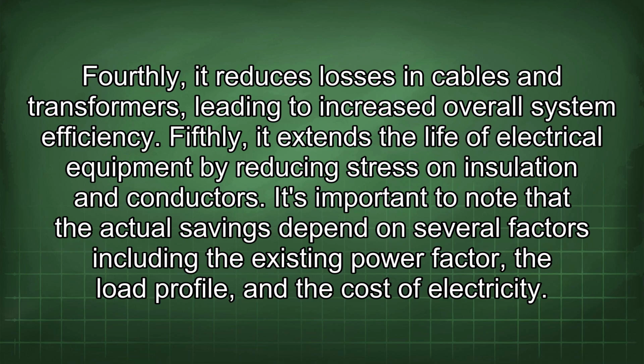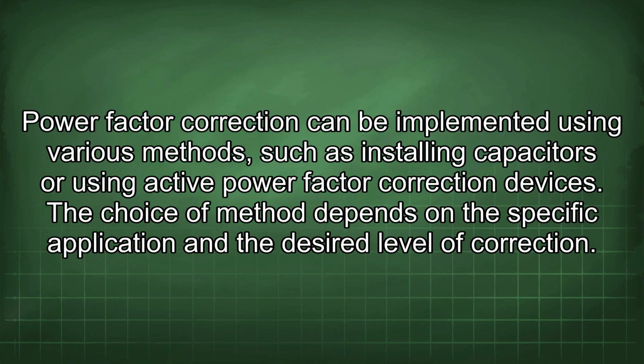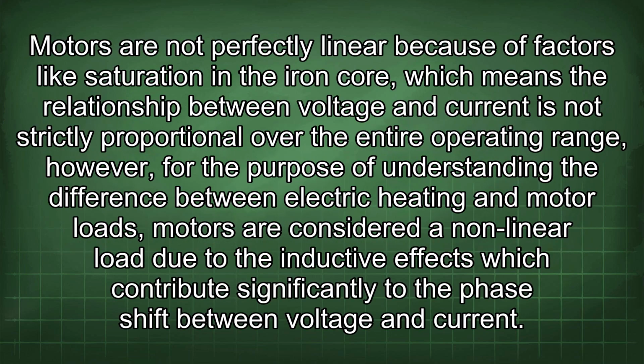It's important to note that the actual savings depend on several factors, including the existing power factor, the load profile, and the cost of electricity. Power factor correction can be implemented using various methods, such as installing capacitors or using active power factor correction devices. The choice of method depends on the specific application and the desired level of correction. Motors are not perfectly linear because of factors like saturation in the iron core, which means the relationship between voltage and current is not strictly proportional over the entire operating range.